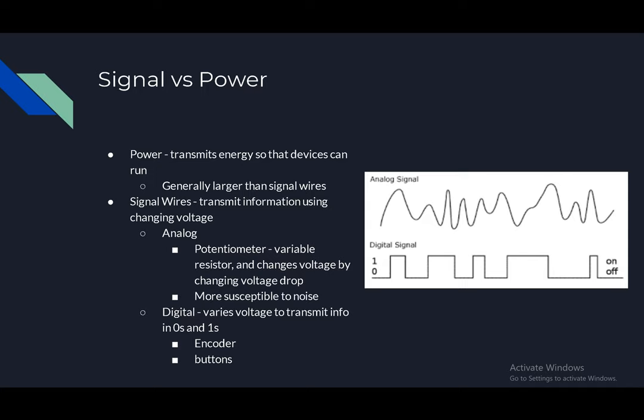Signal versus power wires: power transmits energy so that devices can run, and is generally larger than signal wires. Signal wires transmit information using changing voltage. Analog: uses a potentiometer — a variable resistor — and changes voltage by changing the voltage drop. It is more susceptible to noise. Digital: varies voltage to transmit zeros and ones, using encoders and buttons.